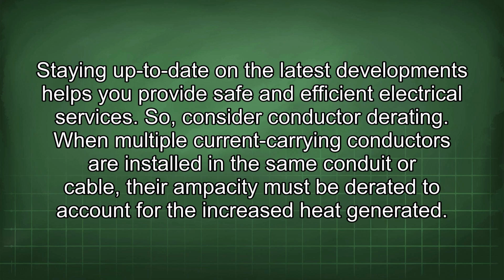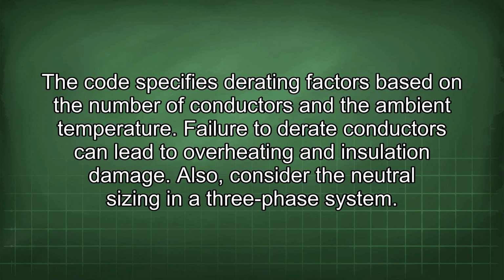So, consider conductor derating. When multiple current-carrying conductors are installed in the same conduit or cable, their ampacity must be derated to account for the increased heat generated. The code specifies derating factors based on the number of conductors and the ambient temperature. Failure to derate conductors can lead to overheating and insulation damage.